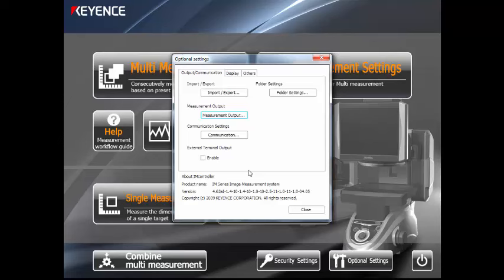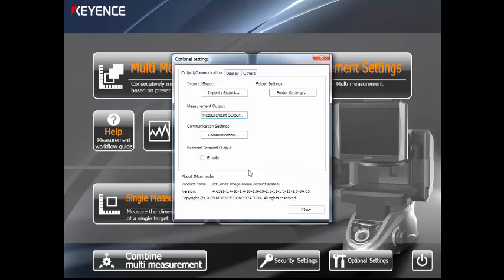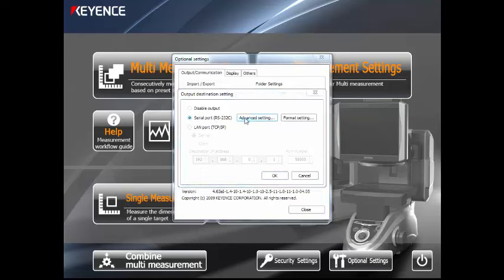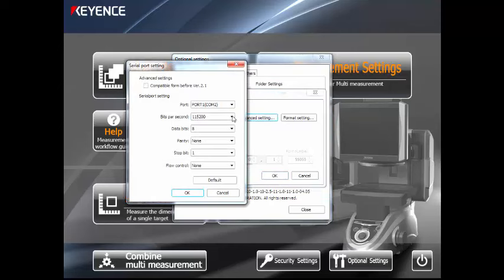If you want to make some fine-tune adjustments to how it works, once you're here at Optional Settings, hold Control, Shift, and the letter S as in SAM. Control Shift S will bring up your RS-232 output settings screen. Serial, you'll notice, is already selected. If you go to Advanced Settings, here's where you can set up the communication settings. This should be at 115200, and if it's not, please change it to that, as this is the fastest communication method.